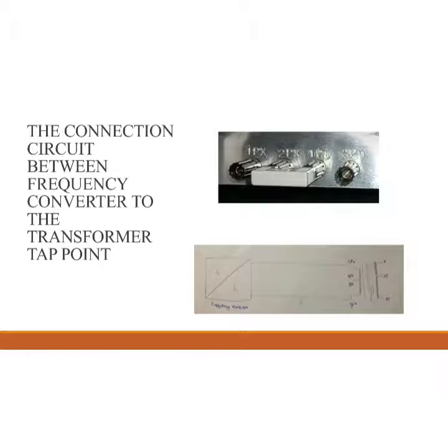And next, make sure that 2PX and 1PU are in contact so we can gain the whole potential from 1PX to 2PU. At the same time, ensure the connection on the side is also in contact to obtain the maximum voltage value from 0 to 100 kV. By using coaxial cable, we must ensure that the impedance value of the coaxial cable is 50 ohm.